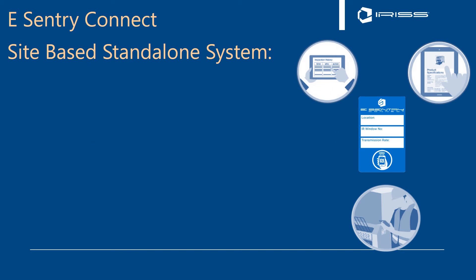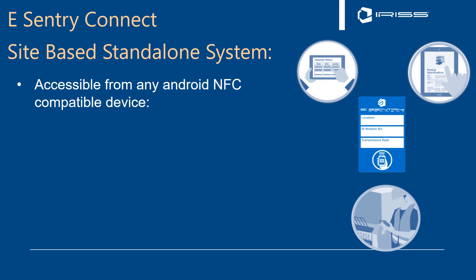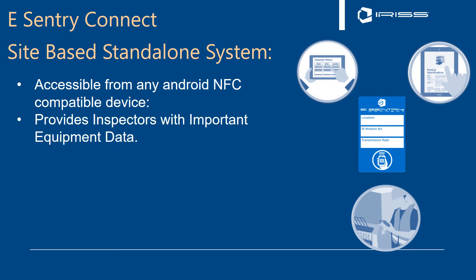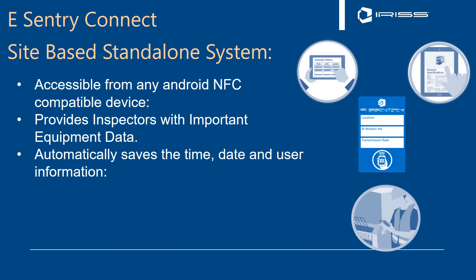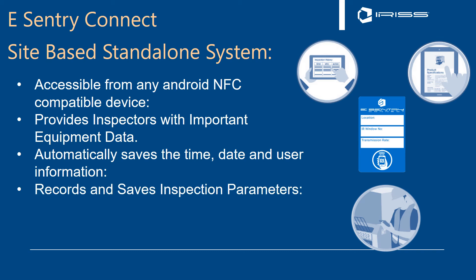The site-based standalone system is accessible from all Android NFC-compatible devices. It provides inspectors with important equipment data — when I open the tag, it tells me the targets, emissivity, and any notes. It automatically records the time, date, and user information, digitally imprinting that tagging operation to the person who opened it. It records and saves all inspection parameters, so I can open the tag, look at the last inspection date and findings — for example, it was at 82°F and there was a warm connection on phase two — and relay that to the next inspector, enabling instant historical analysis.